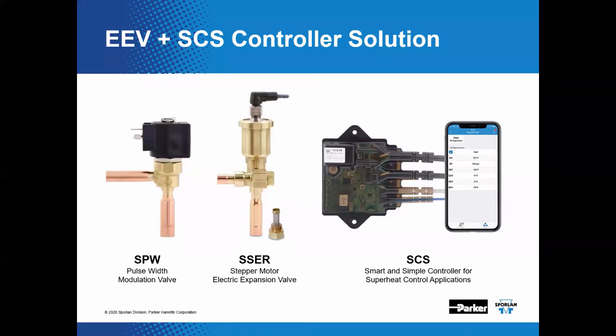That might be a stretch. In days gone by, we used to suggest that the C or medium temp refrigerant application charge was good from a minus 10 degree F to upwards of 40 or even 50 degrees. In recent times, we've learned that we can go down into the 20-degree range. 25 might be a stretch for it, though. But one thing I will say is if you try it, you're happy with the results. I'm not going to argue with that.